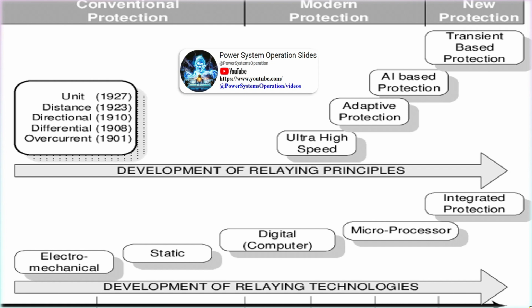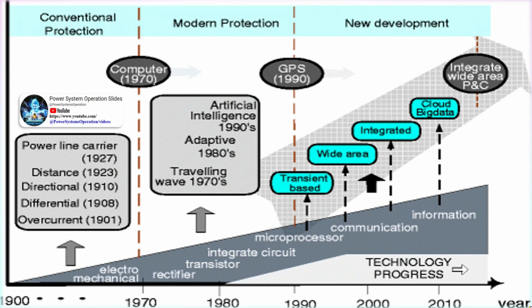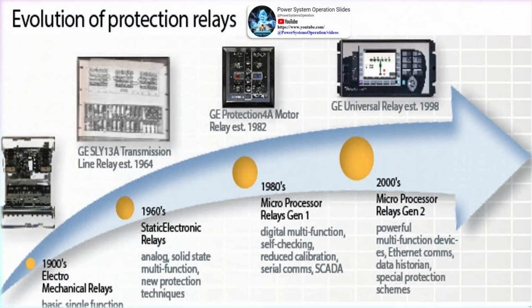In the 1990s, the notion of integrated protection and control became very popular and benefited full advantage of microprocessor technology for protection, monitoring, control, disturbance and event handling, and communication. The relay's volumes as well as wiring were significantly reduced due to the integration of functions and the use of serial communication. It is the job of power system protective equipment to detect the onset of undesired events and take appropriate action. Appropriate action often includes the tripping of circuit breakers. Circuit breaker tripping isolates the trouble from the remainder of the power system and minimizes damage.